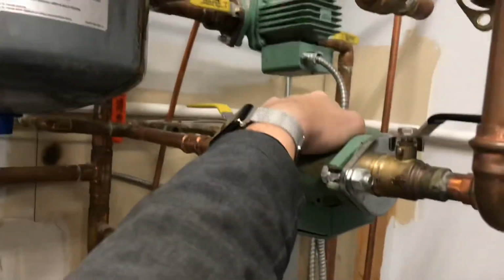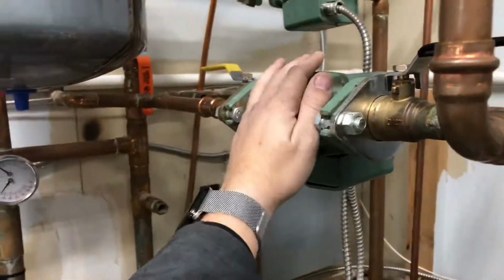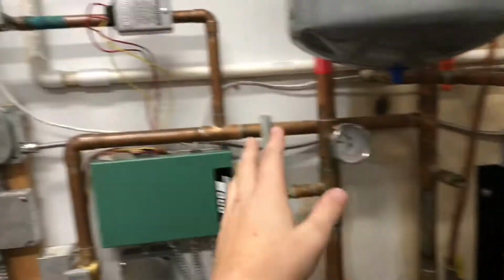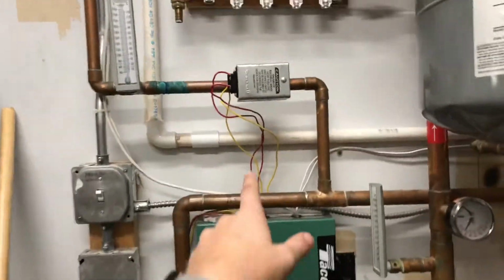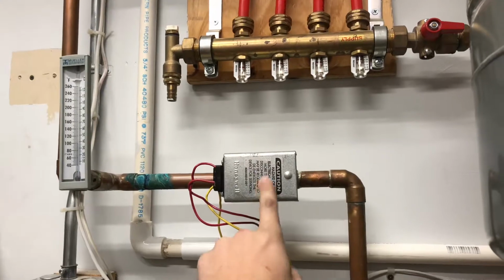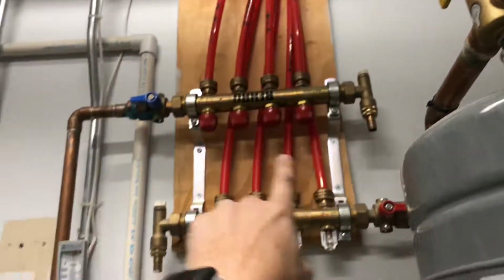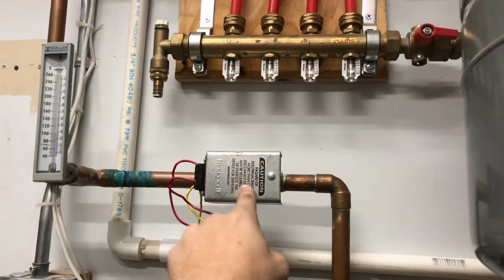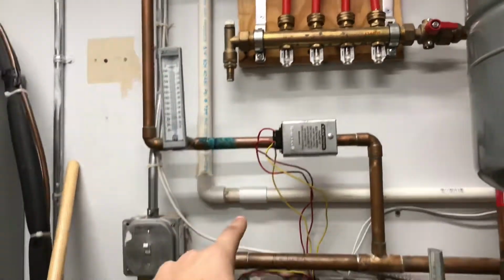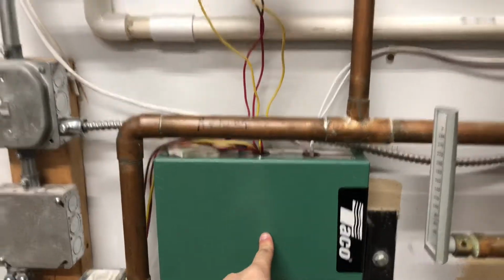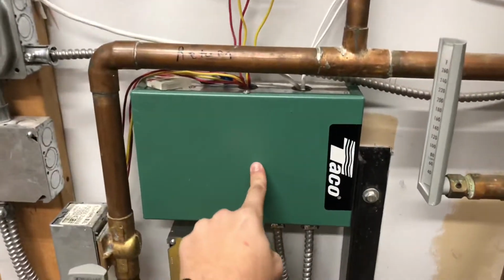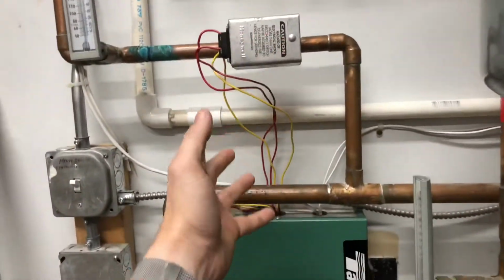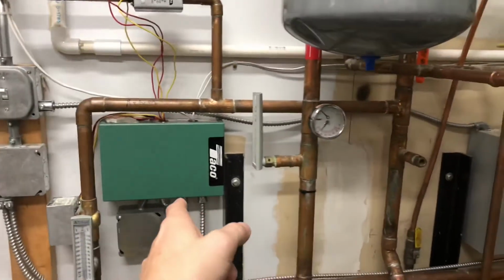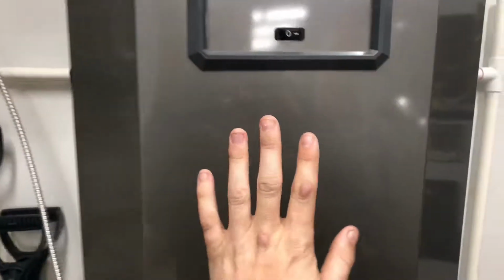You'll wire the 110 volts from the zone pump to your taco. Once you've got that wired into the taco, you're going to need one of these valves on the end. So after it comes out of the return, the next thing you're going to want in line is one of these zone valves. The zone valve is going to talk straight to the taco. So this is going to give voltage to this via a thermostat. Once that happens, the taco will excite the lead lag inside of this, which I'll show you in a second.